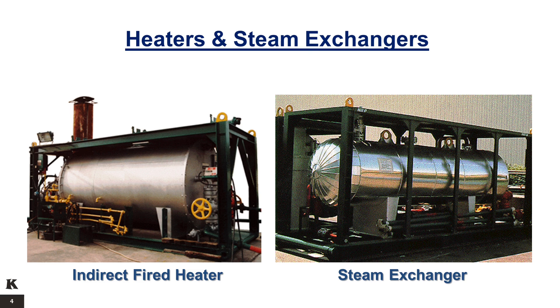An inlet manifold with three gate valves controls fluid flow and provides a way to bypass the coils and choke. To maintain a preset temperature, the steam flowing into the vessel is regulated by a steam control valve (SCV) on the steam inlet. A steam trap is mounted on the steam outlet line. The exchanger requires an adequate steam supply for operation. Some rigs have a sufficient steam supply, but usually a steam generator is required.